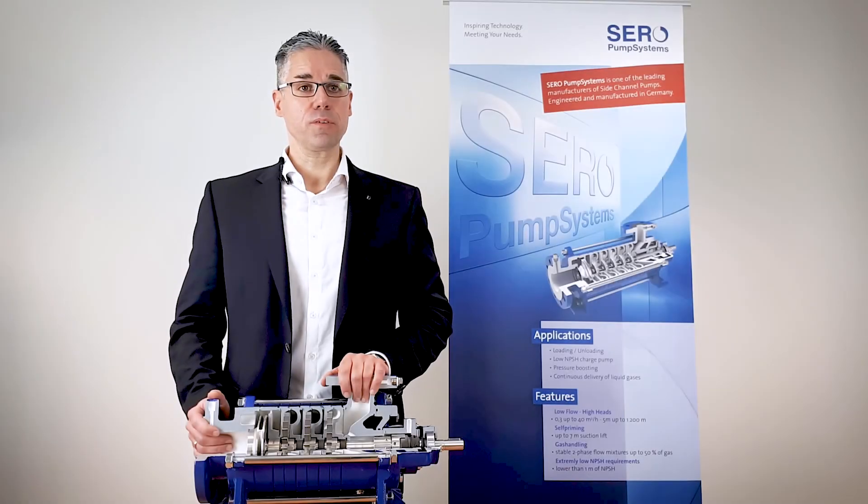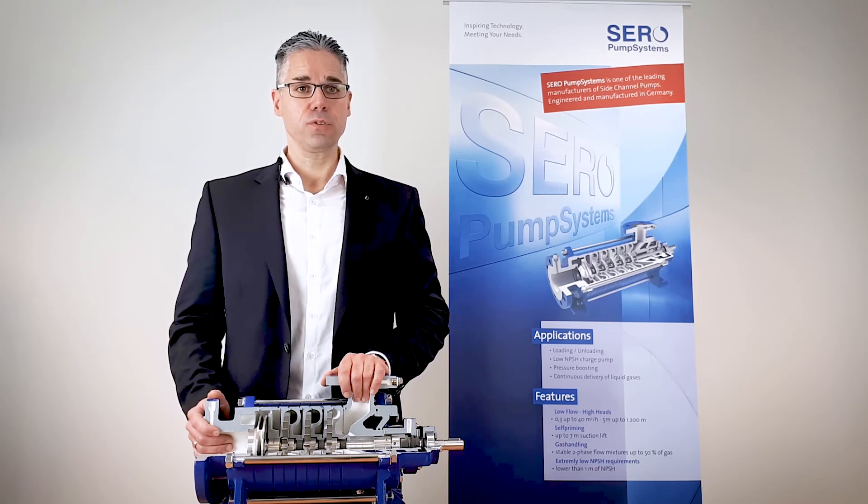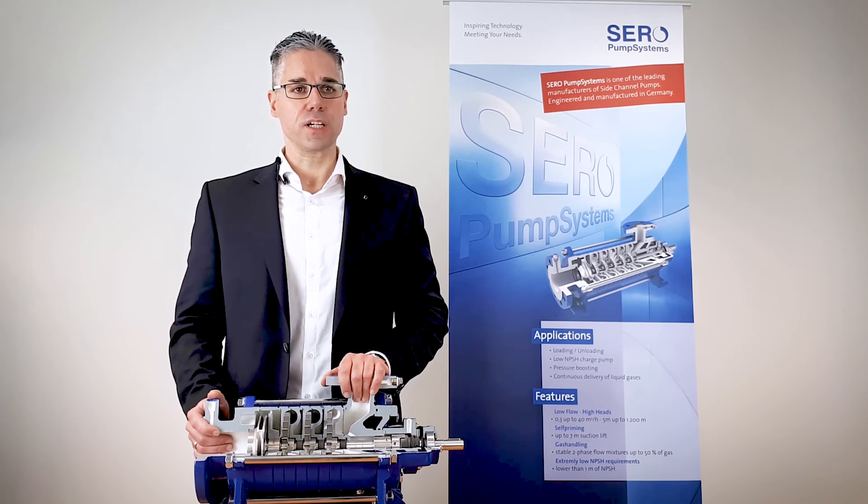And this even more because the mentioned liquids, as well as many solvents, refrigerants, fuels and low specific gravity chemicals, are quite often handled close to their vapor pressure. To avoid flashing of those liquids in the suction eye of the pump, the equipment needs low NPSH requirements. Sero's Multifunction Hydraulics combine the side channel core hydraulics with a specially designed upstream suction stage, providing super low NPSH values which allow to keep your installation simple.